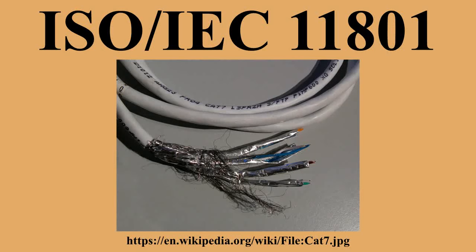Class E: link channel up to 250 MHz using Category 6 cable connectors. Class EA: link channel up to 500 MHz using Category 6A cable connectors. Class F: link channel up to 600 MHz using Category 7 cable connectors. Class FA: link channel up to 1,000 MHz using Category 7A cable connectors. Class I: link channel up to between 1,600 MHz and 2,000 MHz using Category 8.1 cable connectors.